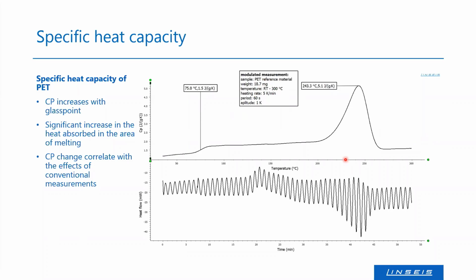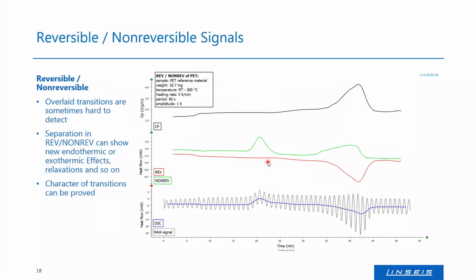This is a recommendation, for example, for PET. Of course, you have to adjust your settings to your sample. This is important. But overall, these are good settings for a first try for your measurement. The next step would be, I've talked also about the reversing and non-reversing part, so let's go on with this. As you can see here, these are now 5 curves, and there is some additional information.